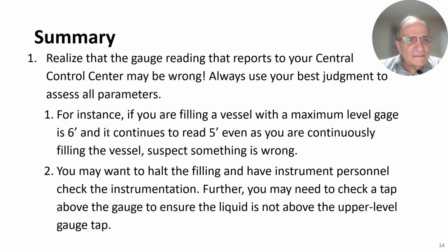Summary. Realize that gauge readings that report to your central control center may be wrong. Always use your best judgment to assess parameters. I remember one time where a control board operator was at the board tapping the gauge, wondering why it was pinned, not realizing that if he would have stepped back, he would have seen that all the gauges were pinned. The system was overpressurizing.